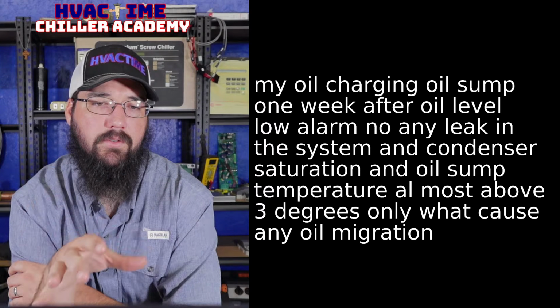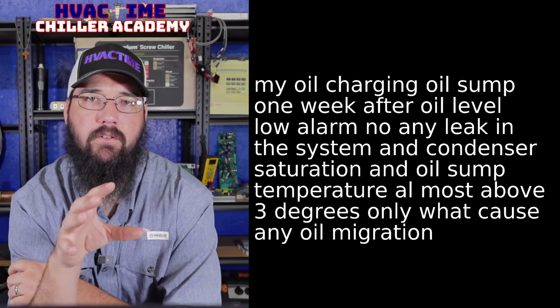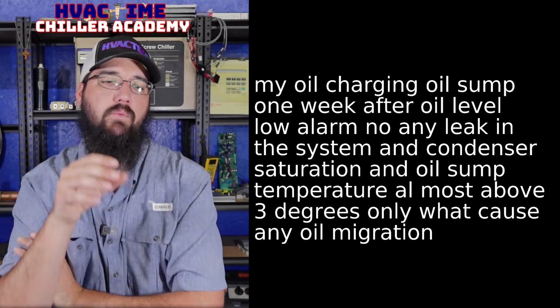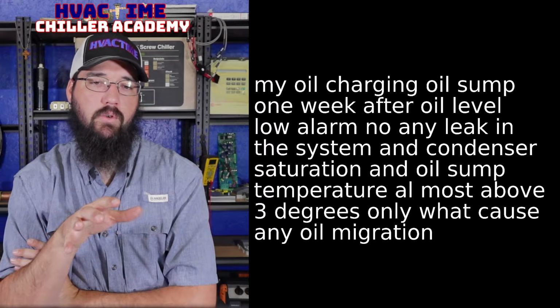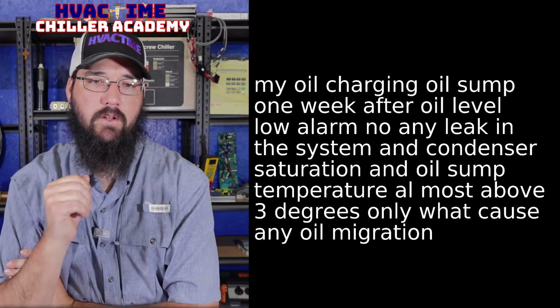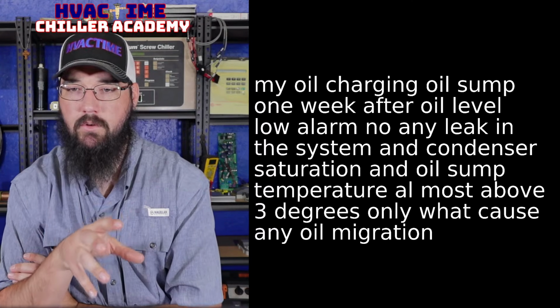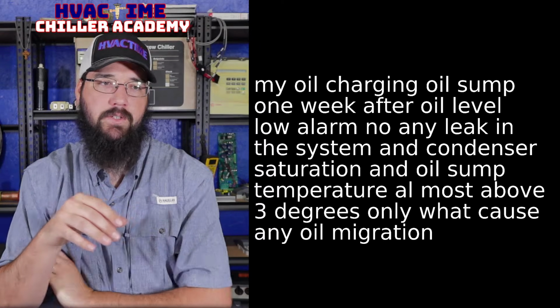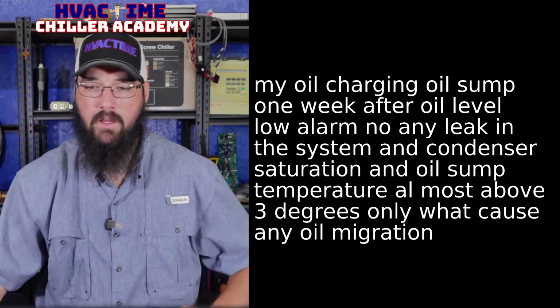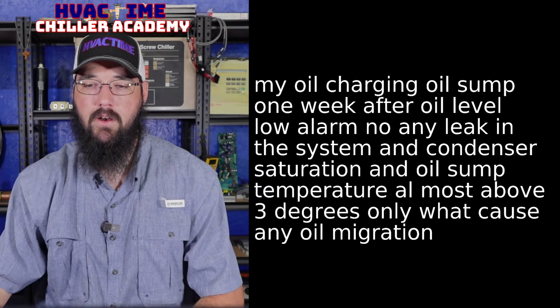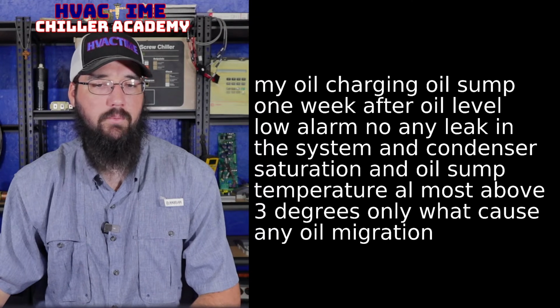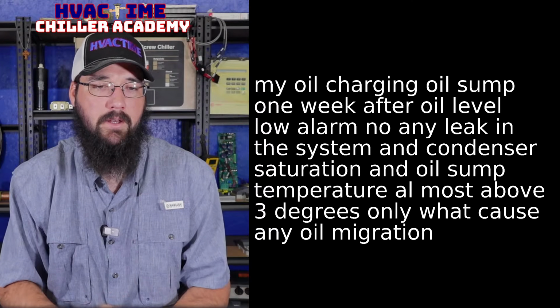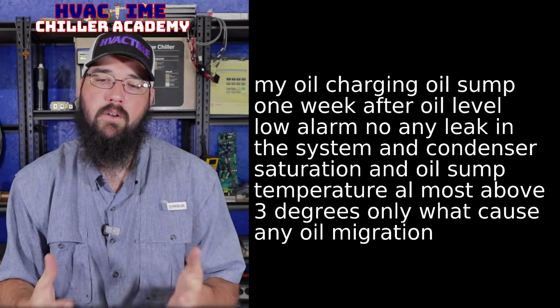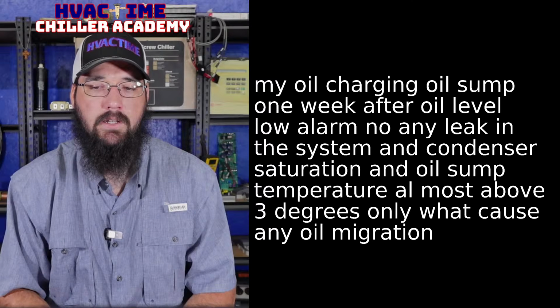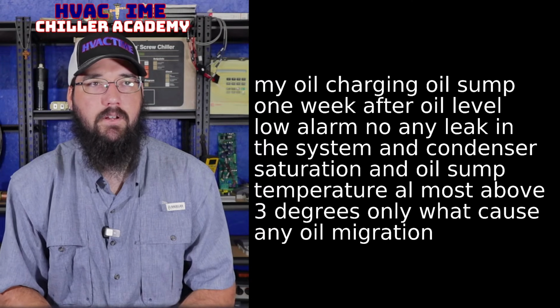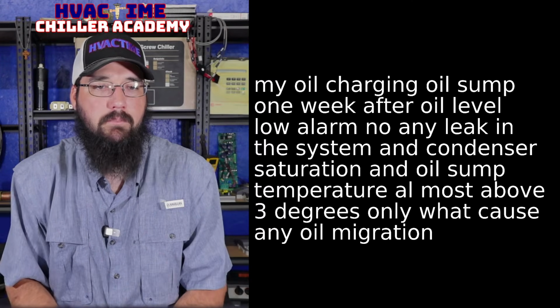Okay, so we're having low oil alarms. We don't have any oil leaks. If we did, there'd be a ton of oil on the ground. We don't know what machine we're working on, but just from a general standpoint, it gives us something to start with. If you want to tell us what model we're working on here, that could be helpful. It may not make much of a difference. There are some models that have a little bit more variance in how they perform.